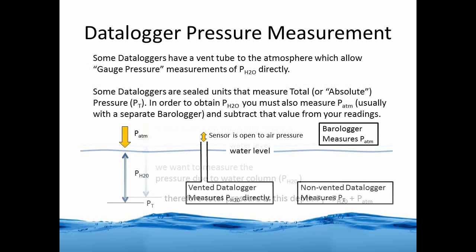Let's look at how data loggers measure pressure. Some have a vent tube to the atmosphere, which allows gauge pressure measurements of the water pressure directly. Some data loggers are sealed units that measure the total or absolute pressure. In order to obtain the pressure of water above, you must also measure the pressure of the atmosphere — usually with a separate device called a barologger — and then subtract that value from your pressure readings of water.